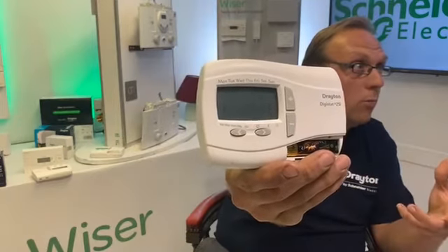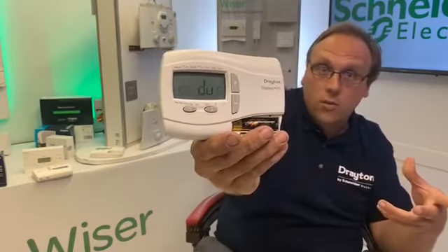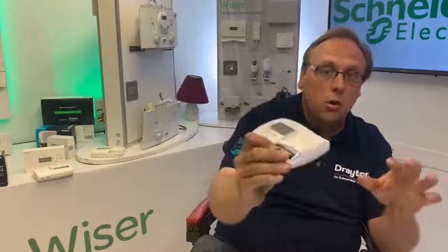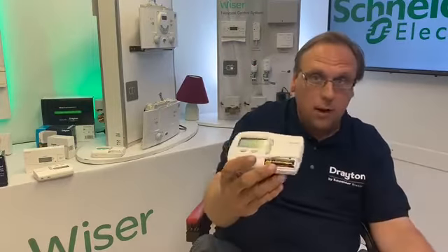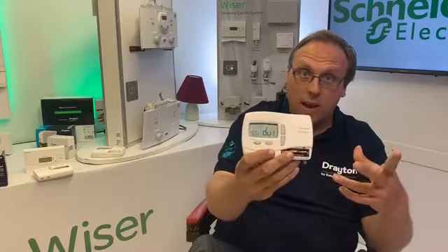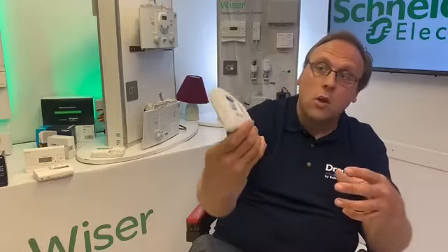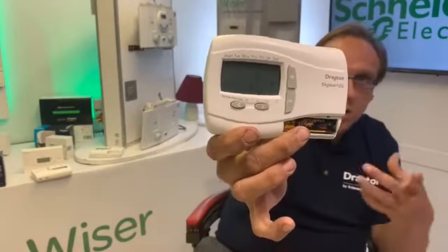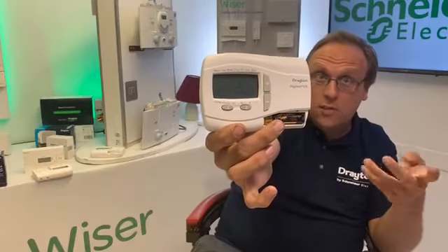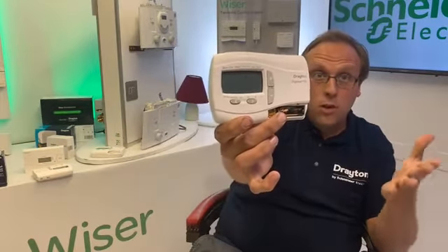So if you need to be setting service intervals for local authority, you can do it with the Digistat SI range. We do a plus 3 as well in that range. But in terms of programming, it's exactly the same. The customer wouldn't know any different. All you get is the capability of going in and setting it up. You don't need the reset key for this. It's done on a passcode that you put in.